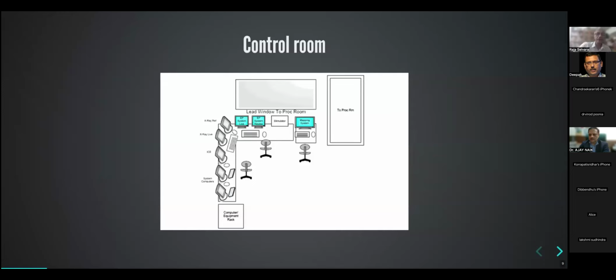Now, when you have the control room set up outside, you can have two monitors for the EP system, and a monitor for the 3D mapping system and the stimulator. A lot of the sound systems usually have a push-to-talk feature, but there are systems which are always on. For this kind of setup, it's better to have a duplex, always-on sound system, so that two-way communication is always open.